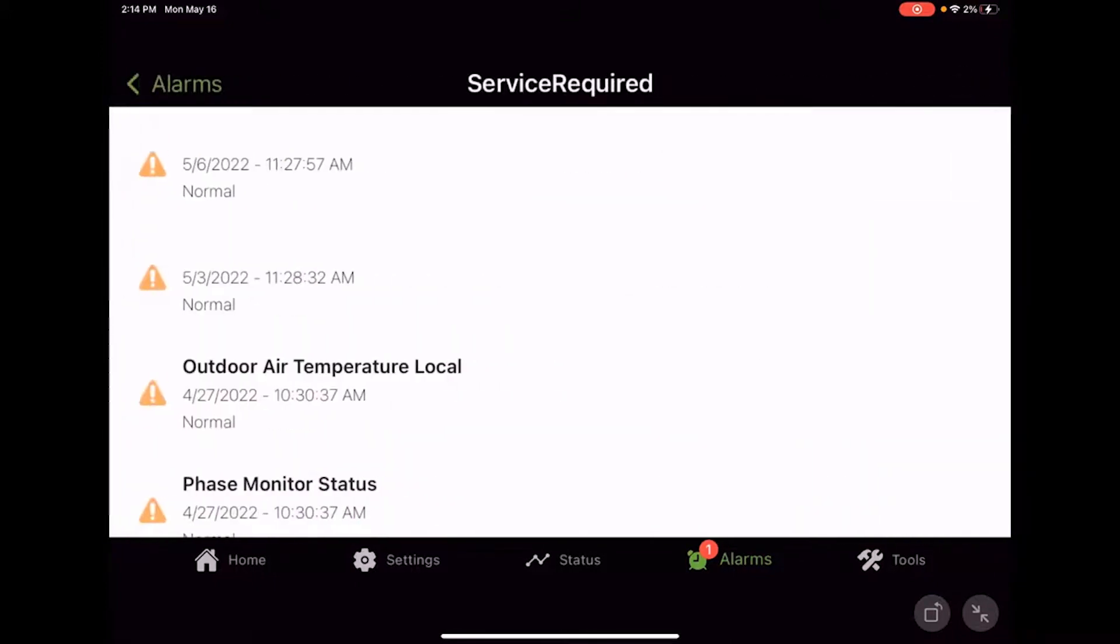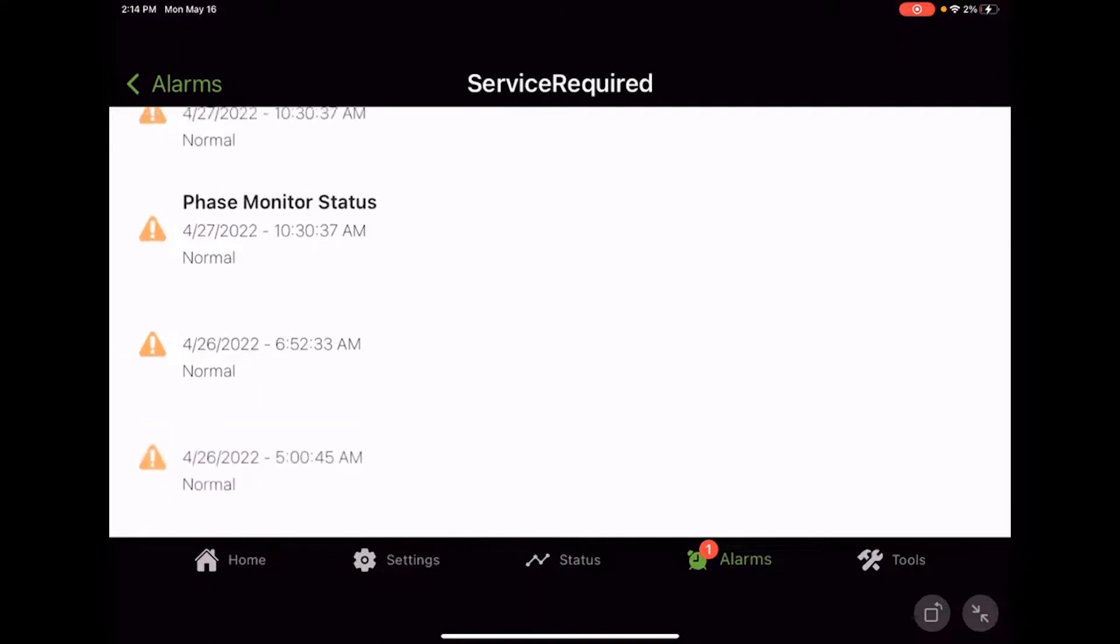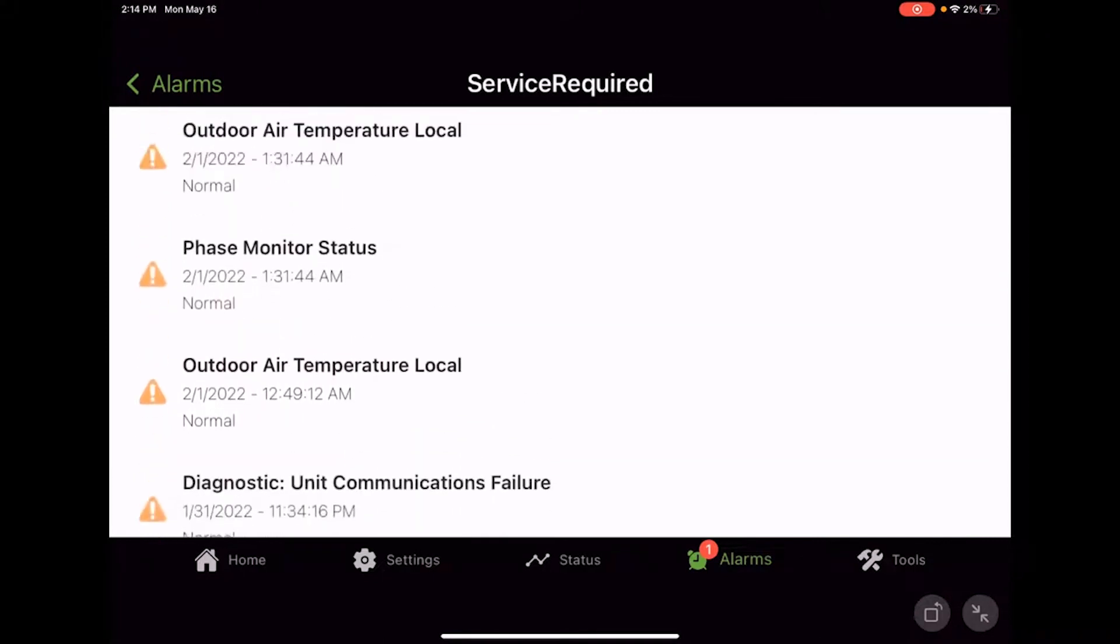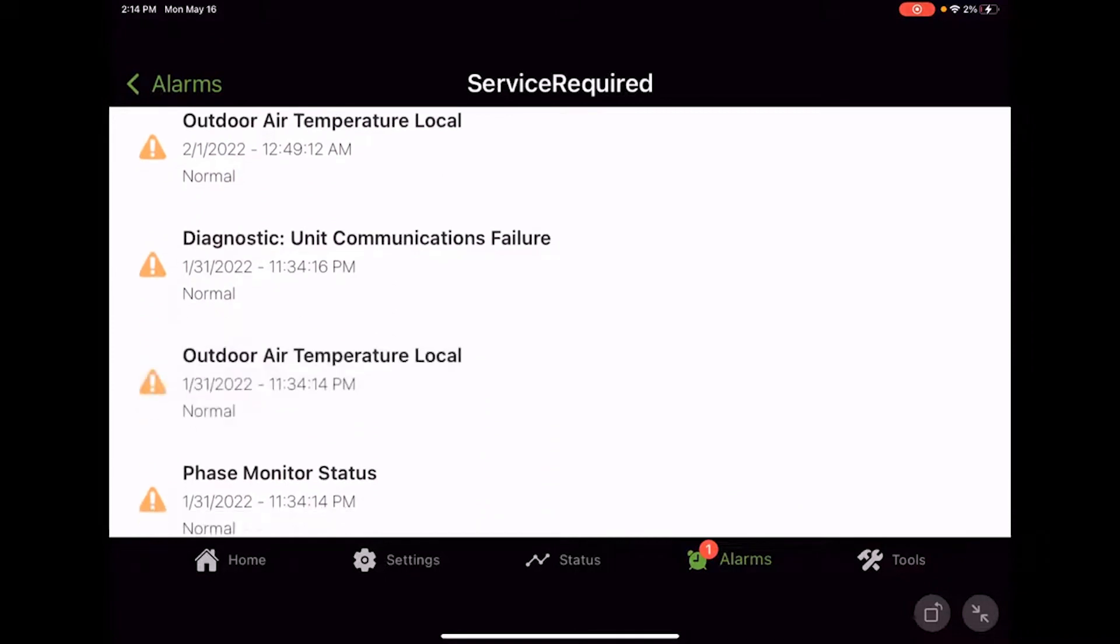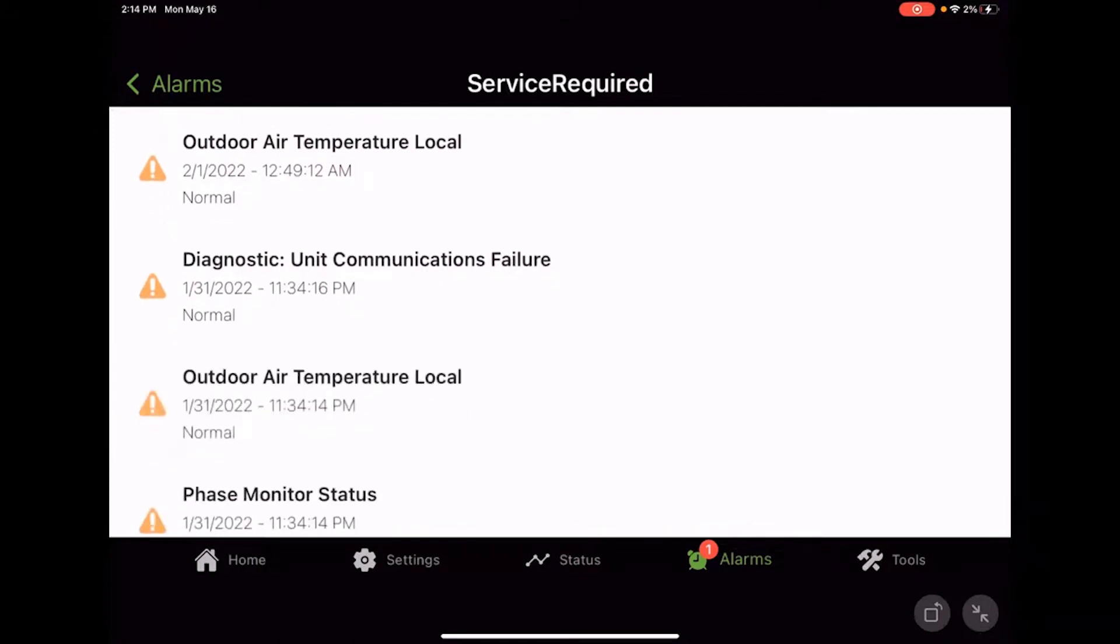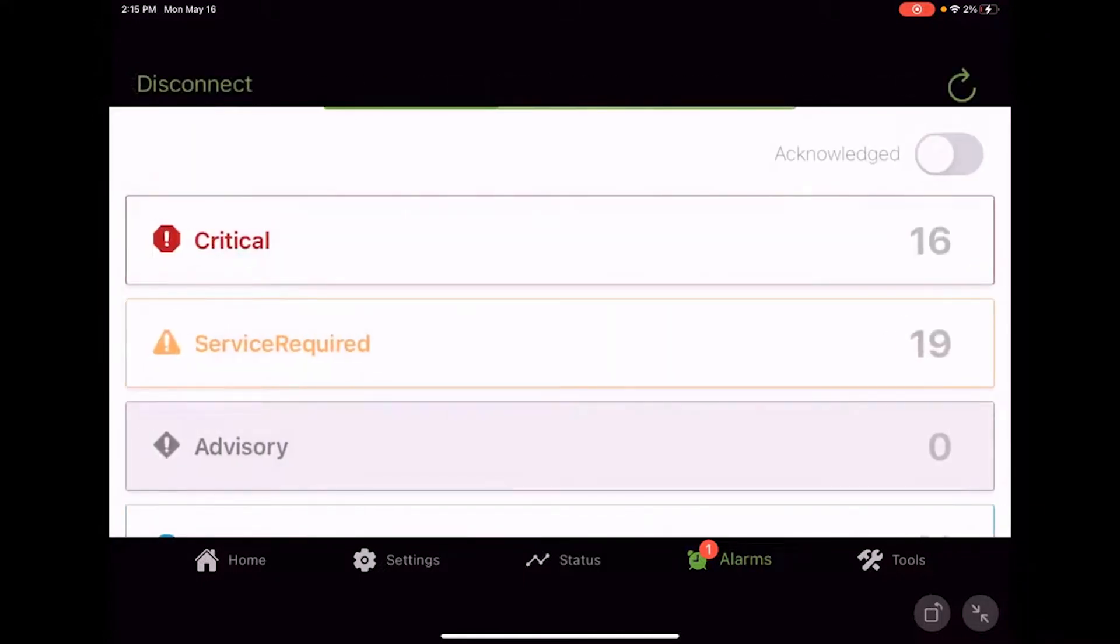Service required is important stuff. We need to really check it out. It requires some service, but it may not be something that's going to lock out or prevent the unit from operating. Some things may, some things may not. Outdoor air temp, we need to know that, but it's not going to keep us from working necessarily. Phase monitor status, if that's not normal, that's going to be an indication that we can't run. So we've got lots of fun here with the outdoor air temperature and the phase monitor unit communications failure. So this unit lost communication at some point. So just general service required, important information, things we need to look at, things that could become a major problem, but they're not quite there yet.